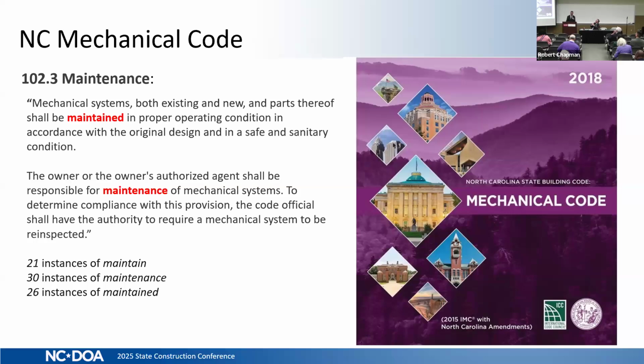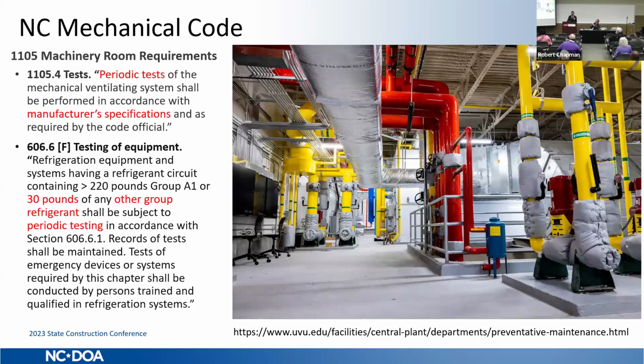In the same format, we see in the North Carolina Mechanical Code the number of instances that maintenance is addressed. And that includes periodic testing. Certain pieces of equipment need testing as well as maintenance. In this case, it's the ones that contain refrigerant. You see here, if you have the common refrigerant, the A1 refrigerant, you need to have more than 220 pounds of it before you're kicked into the code required periodic test.